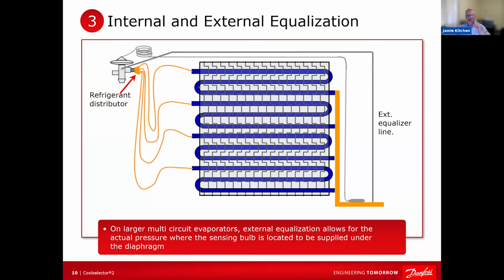And so what ends up happening is the saturation temperature, or the actual temperature in your evaporator, could be 10, 15 degrees less than what the TXV thinks it is. Okay. So if the TXV thinks it's 45 degrees and it's actually 35 degrees because of the pressure drop through the distributor, and if your sensing bulb needs 7 degrees of superheat to open, again, it thought it was 45 and 35.